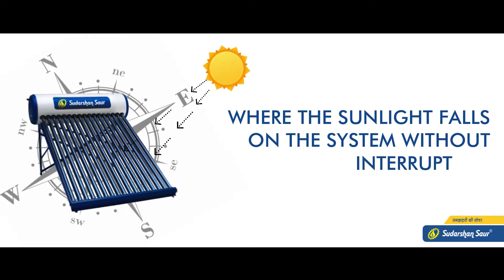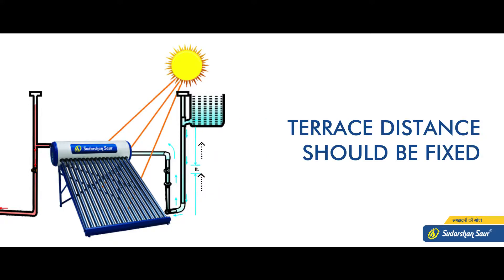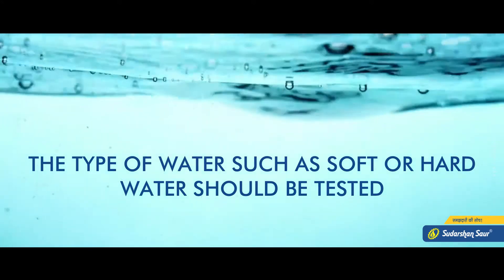Site surveys are extremely important when installing a solar water heater. To set up the system, the place should be such where the sunlight falls on the system without interruption. The height of the cold water supply tank and terrace distance should be fixed as per the manual. The type of water, such as soft or hard water, should be tested.